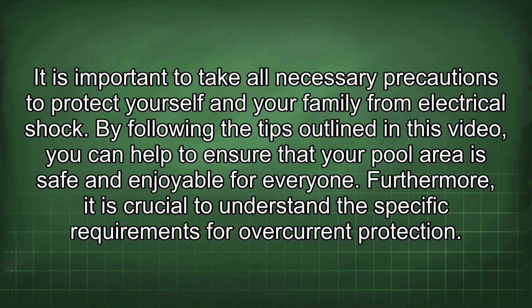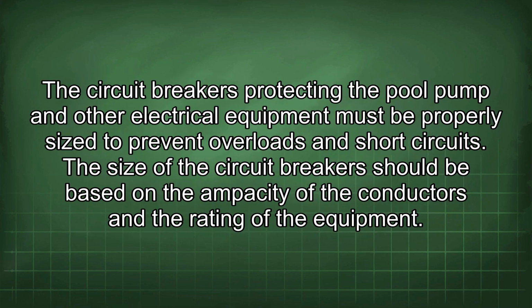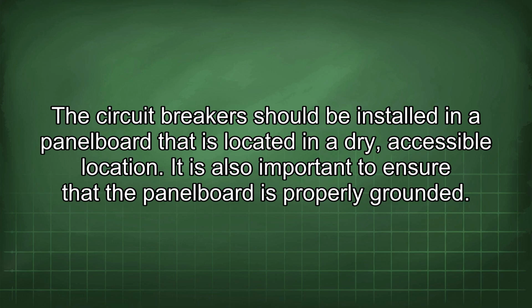Furthermore, it is crucial to understand the specific requirements for overcurrent protection. The circuit breakers protecting the pool pump and other electrical equipment must be properly sized to prevent overloads and short circuits. The size of the circuit breaker should be based on the ampacity of the conductors and the rating of the equipment. The circuit breaker should be installed in a panel board that is located in a dry, accessible location. It is also important to ensure that the panel board is properly grounded.